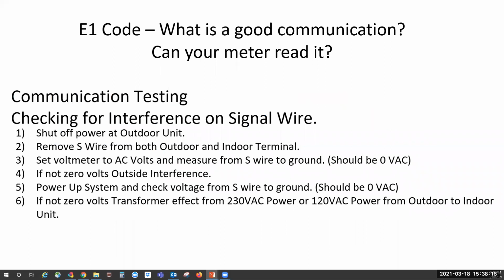Now we're going to check for any interference on our signal wire. You want to shut the unit off. Remove the S wire from both the indoor and the outdoor unit terminal block, and position the wire where it's not going to touch any surface, but you can still access it. Set your meter to AC volts. Remember, our unit's still off, and you're going to check from the S wire to ground, and there should be 0 volts. If you have voltage, you're getting voltage from an outside source of interference, like a transformer on a fluorescent light, something like that.